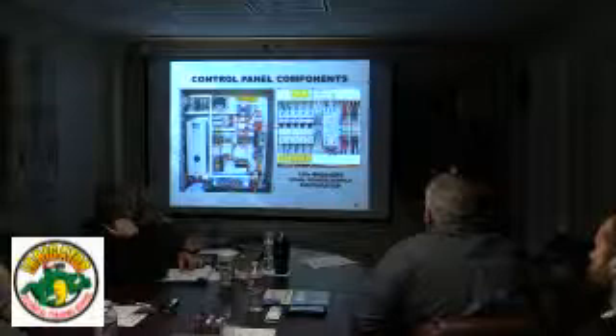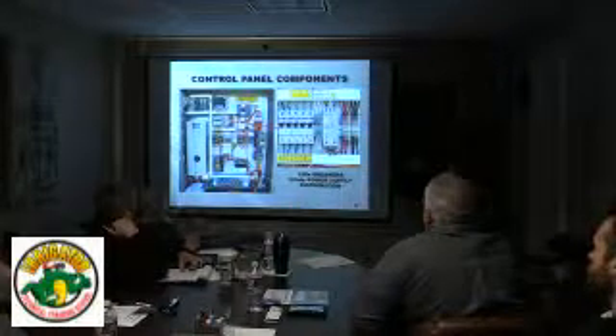It's labeled right here, CB1, 2, 3, and 4. You can look on the schematic, you can see that breaker. So if one's tripping, you can look on the schematic, see where that circuit goes, and narrow it down to maybe just a few items of what might be causing that circuit breaker to trip.